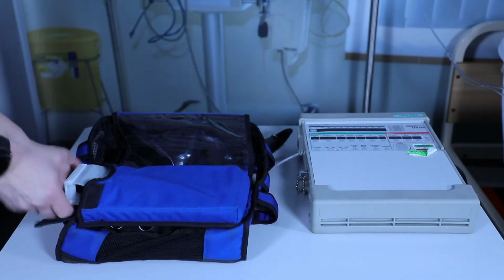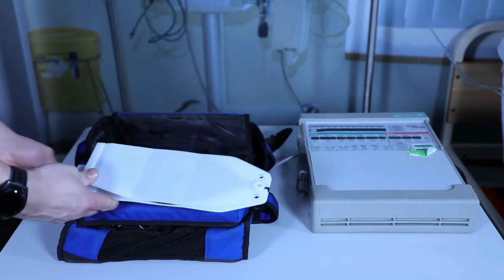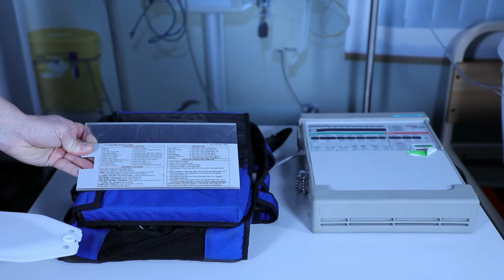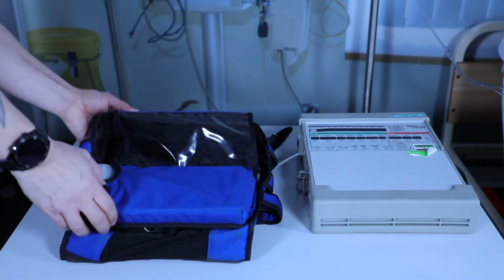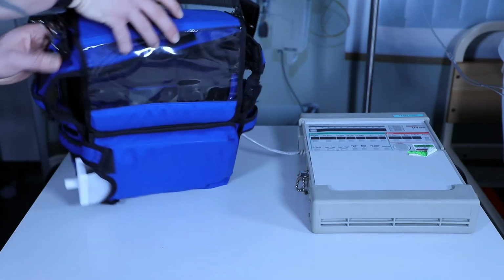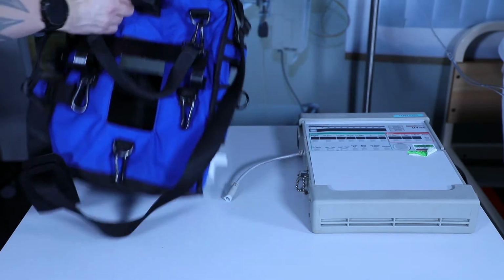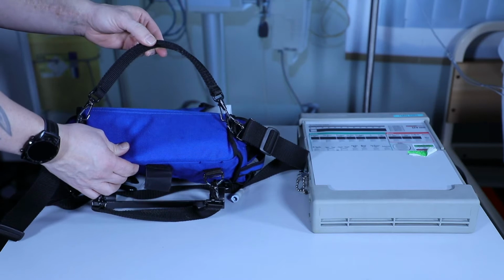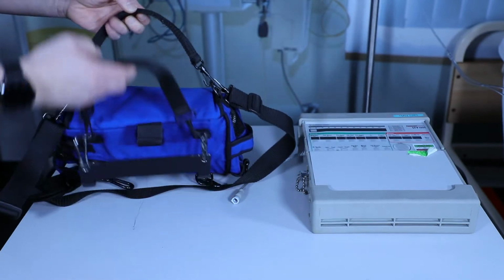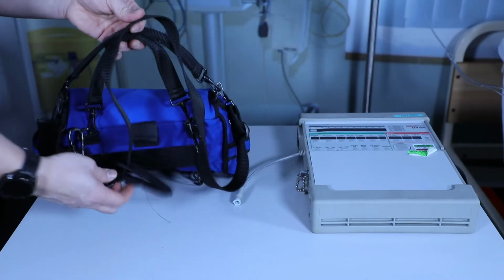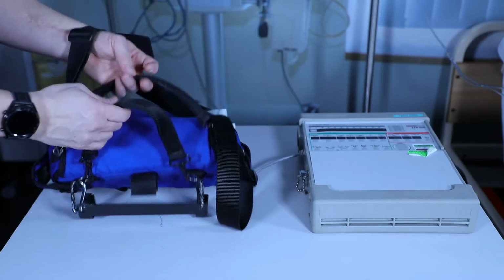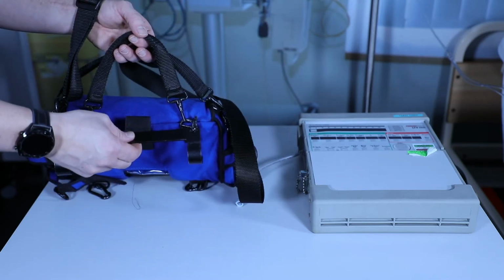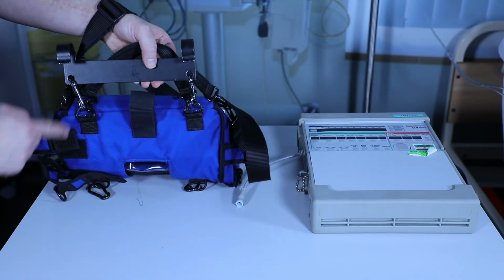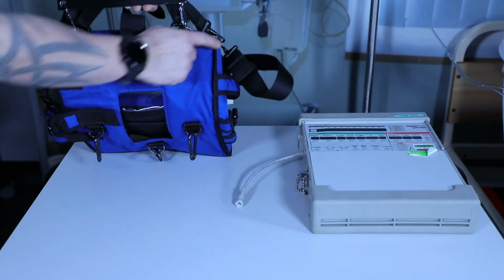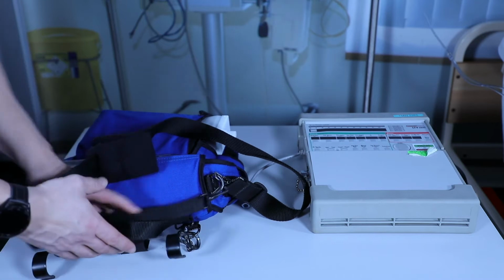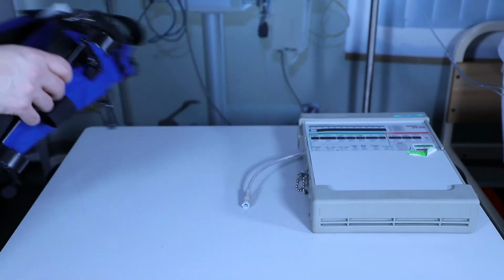We need to confirm in the front pouch of the carry bag there is a test lung and a screen protector. Once we're happy with this, we can place these back into the bag. We then need to inspect the carry bag itself, checking for any dirt or any obvious signs of damage. We want to pay particular attention to the carry handle along with the shoulder strap and ensure that these remain intact. We then need to pay particular attention to a number of D-rings, 5 in total, on the back, and ensuring that the material also remains intact. So once we're happy with that, we can pop the carry bag to the side and focus on the LTV.